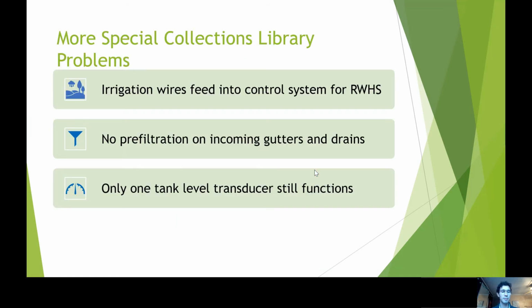Some problems that I didn't put into pictures. There are some irrigation wires that feed into the control system for the rainwater harvesting system. And this demonstrates a sort of misunderstanding of what the system was meant to do. The system was not meant to control the irrigation system. It was meant to simply provide pressurized water. In addition, as I mentioned before, there's no pre-filtration on incoming gutters and drains, and only one tank level transducer still functions.